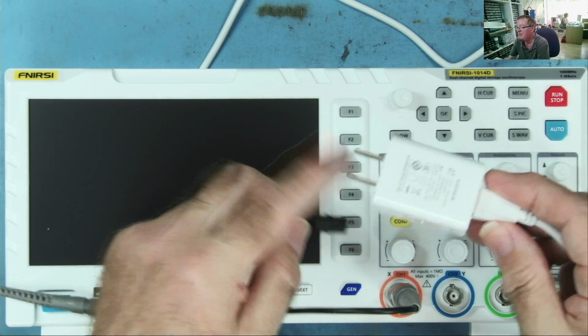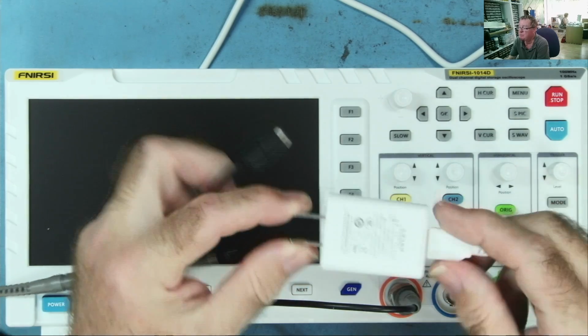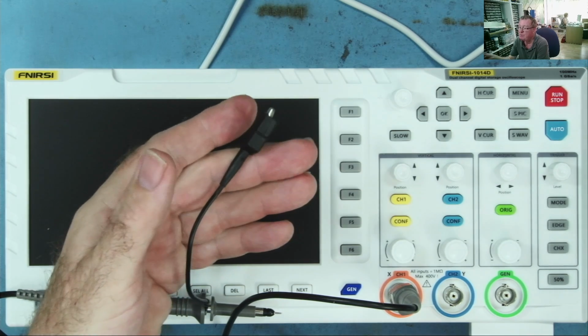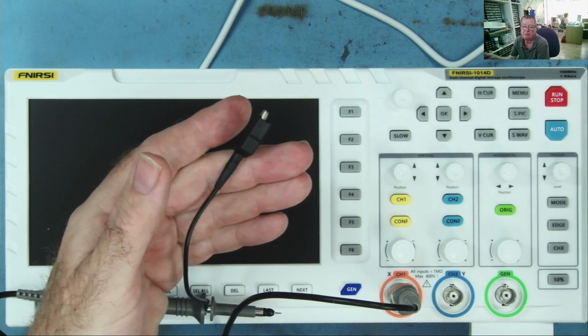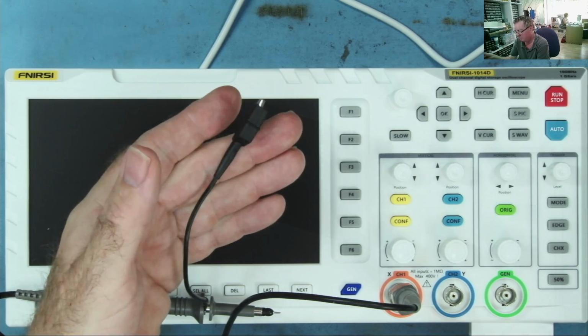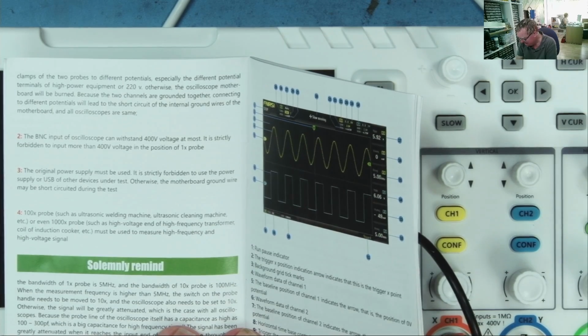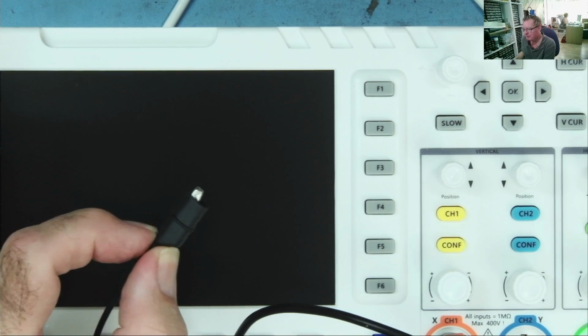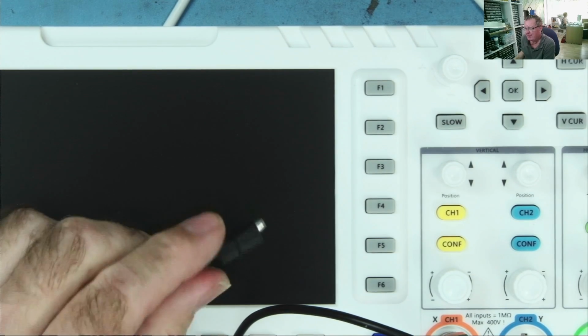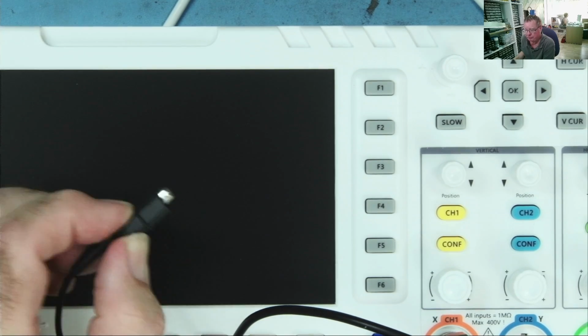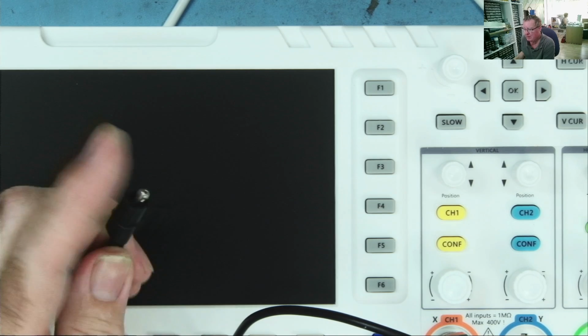So that is a very important thing, and it's nice to see that this is stating this has isolation from safety ground, which means we can connect this scope probe to anywhere on a hot ground, on a switch mode power supply, for example, quite safely. Having said that, there is a caveat, and there often is, isn't there? So the caveat is that when you connect this to hot ground, you're effectively connecting it to live and neutral via the bridge rectifier diodes, depending on which half cycle of the mains. This is live or neutral, and it's changing 50 or 60 times a second. So this is basically a high voltage.